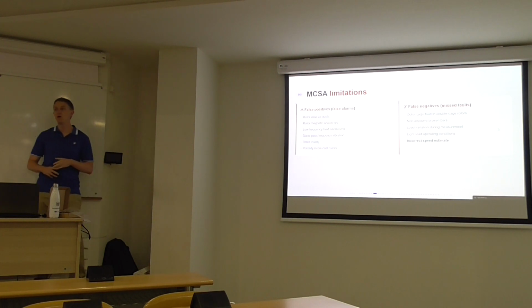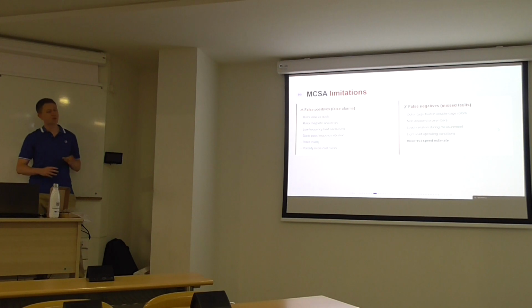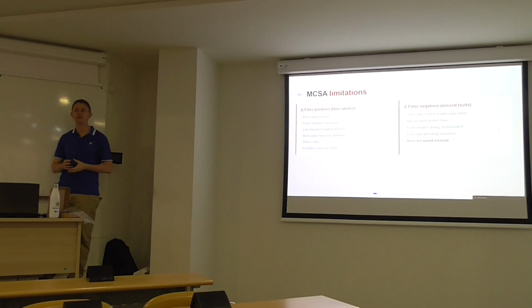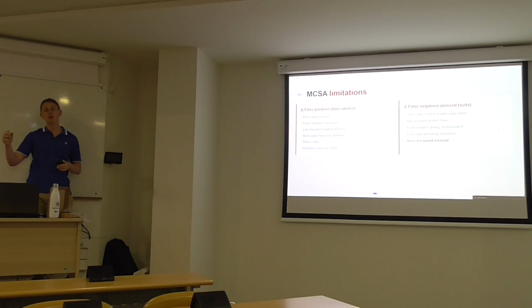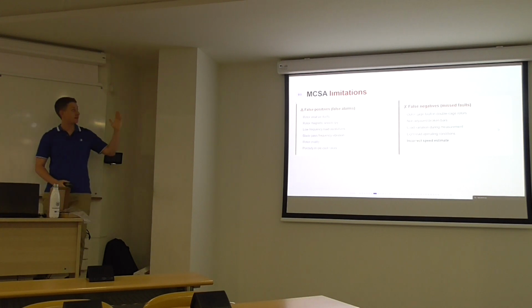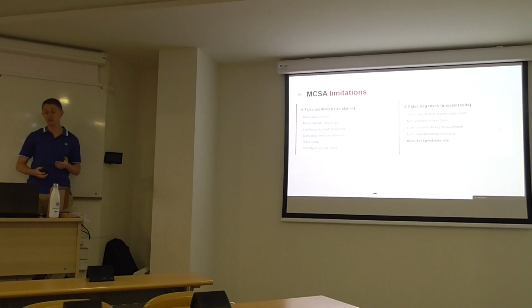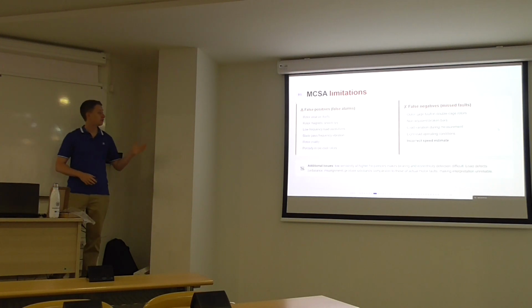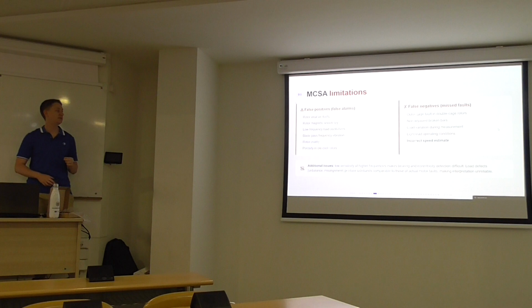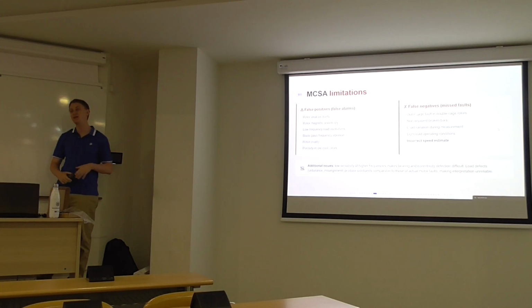Well, many of these problems can be solved if we perform a transient analysis of the startup, or we conduct continuous monitoring. That is, to take measurements of the motor with a short period of time between them. However, in any case, there are inherent limitations of MCSA. And as additional issues, we also have low sensitivity at higher frequencies because the stator winding and the rotor winding act as a low pass filter. So it's more difficult to detect eccentricity and bearing faults.